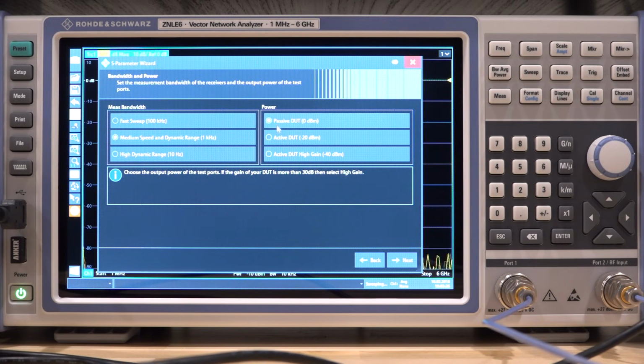microwave filter. Now, this is a passive device, so I'm going to have the incident power at 0 dBm, which is set over here. It'd be nice if this instrument actually had 10 dBm output power, because for some of the very lossy systems, 10 dBm would be useful, or for some very far crosstalks, higher power would be good so that you'll be within the dynamic range of the instrument, but it goes only to 0 dBm, so we're going to do the maximum we can. And we go next over here.